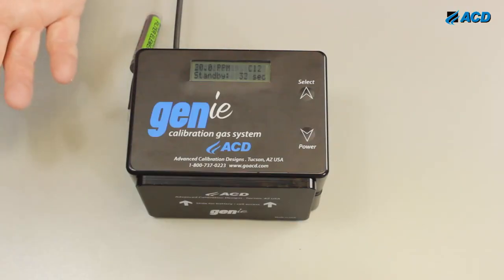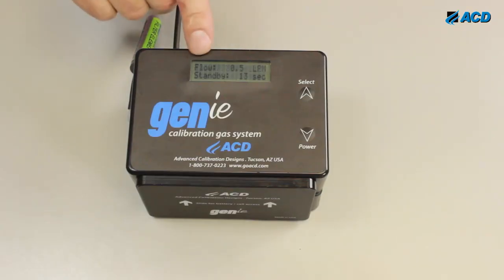And if I'm calibrating a sample draw unit, I can shut the pump off and then attach the GENie unit to the sensor that's got a sample draw unit. It will measure the flow rate for me, and then I can set the output anywhere I want to. All right. So as you see, this is running 0.5 liter a minute, 0.5 and 20.